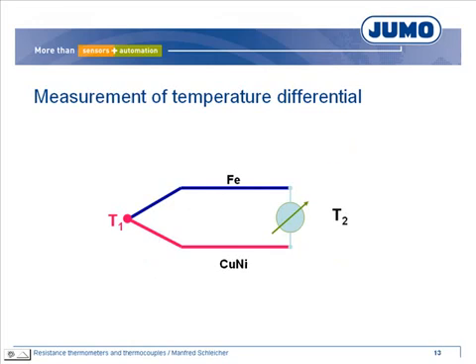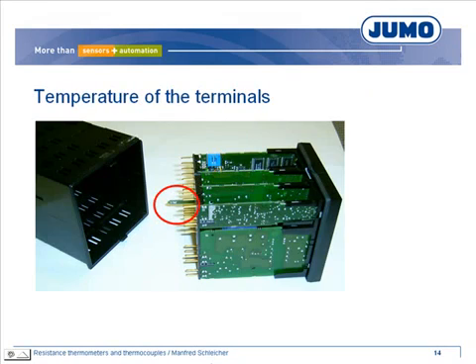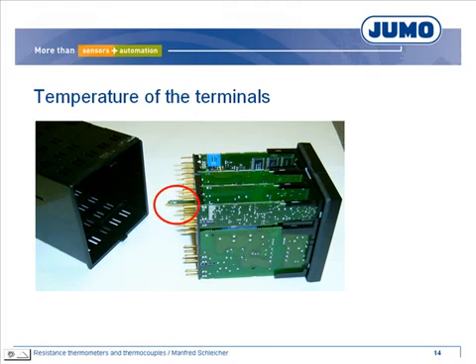Using a thermocouple, you can measure a temperature differential: temperature 1 minus temperature 2. Temperature 1 is the measured temperature and temperature 2 is the so-called reference temperature. To measure temperature 1, you must know temperature 2 and add up the values. Temperature 2 is the temperature of the terminals of the field device, measured by an additional temperature sensor. The temperature of the terminals is added to the calculated temperature differential — this is called internal temperature compensation.